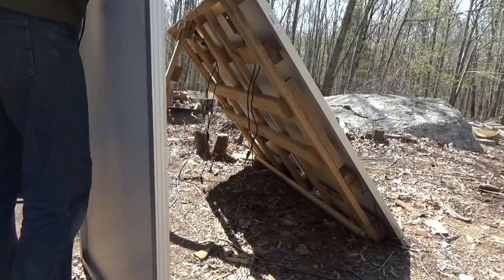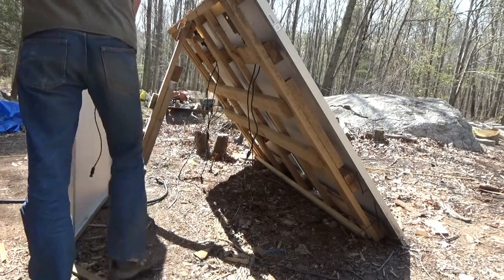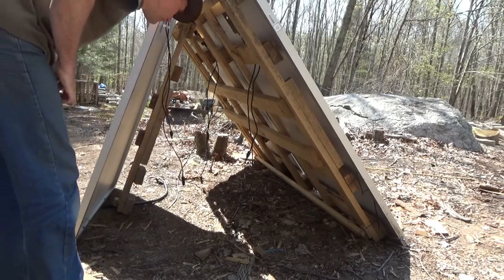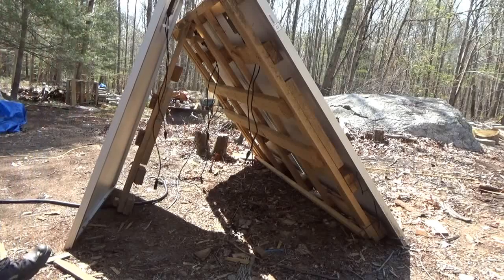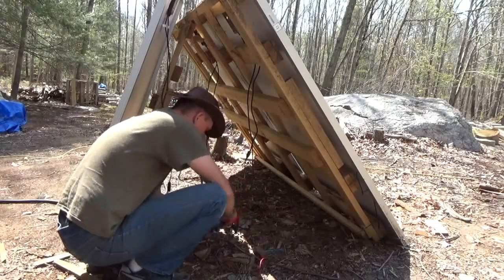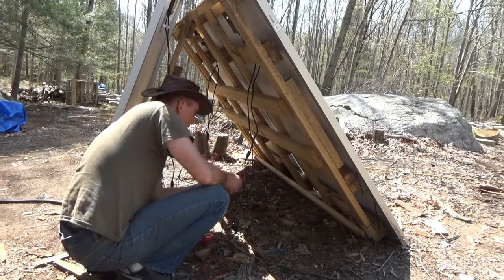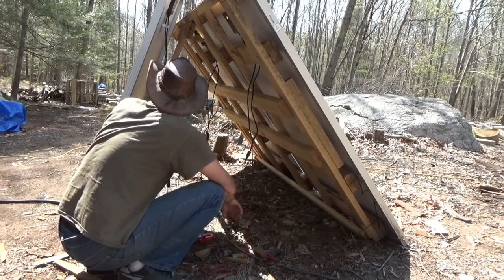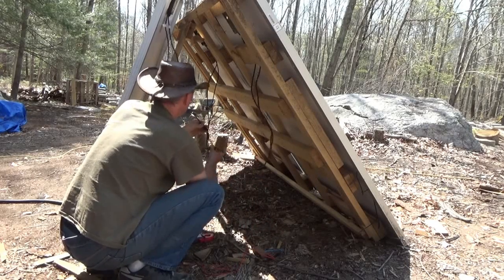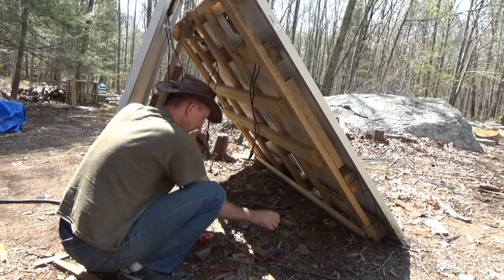It's awkward because the connectors don't reach very well. All I've got to do is get some sunlight on there and find something that works — figure out which panel has a bad connector. But the problem is when I put the meter in, it makes a good enough connection. If I can figure out which panel has failed, we'll be good to go.